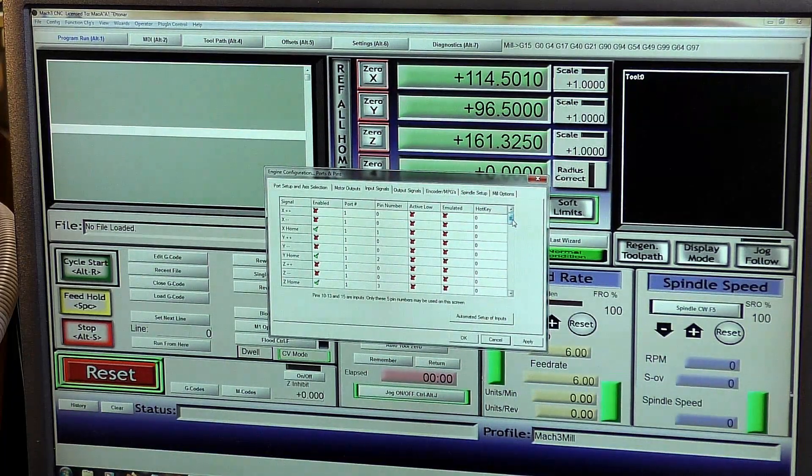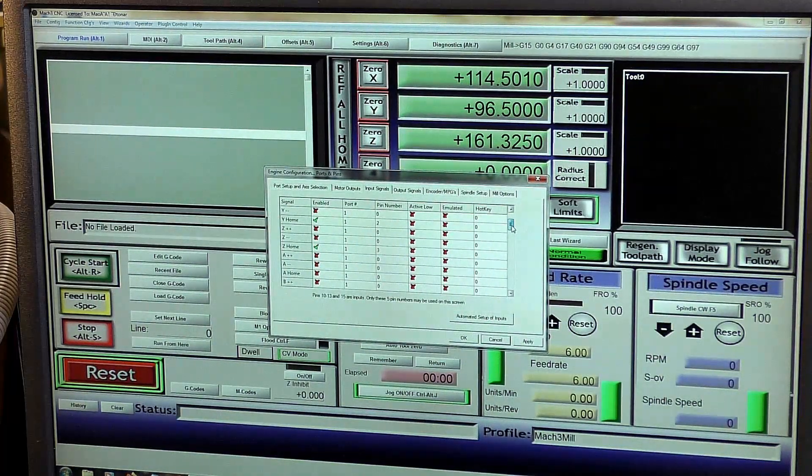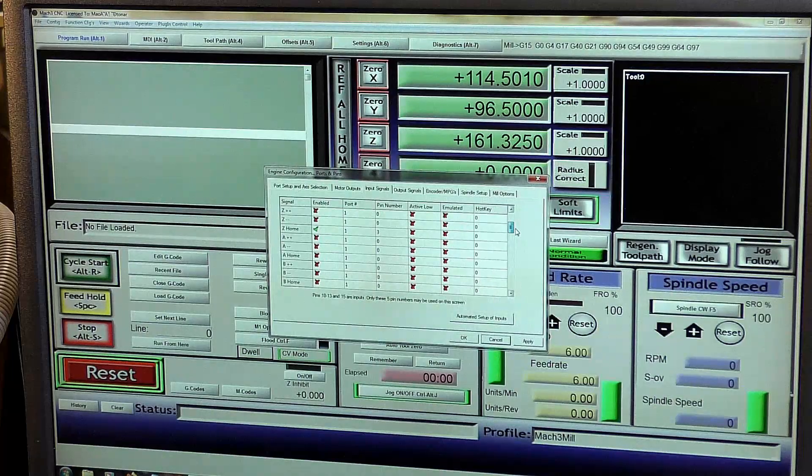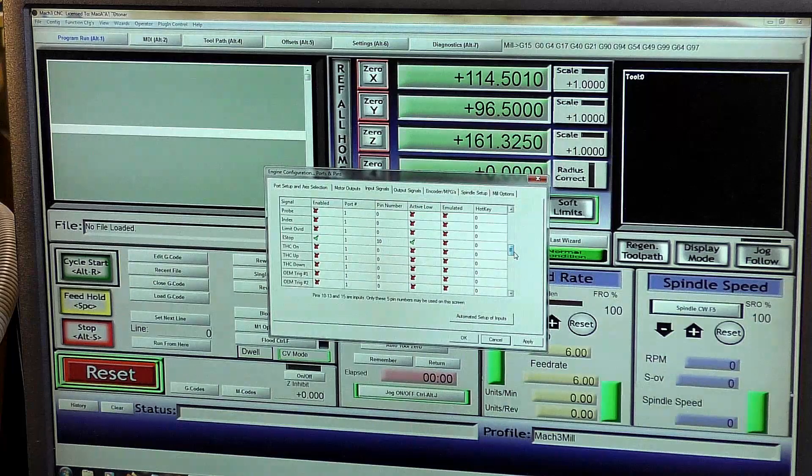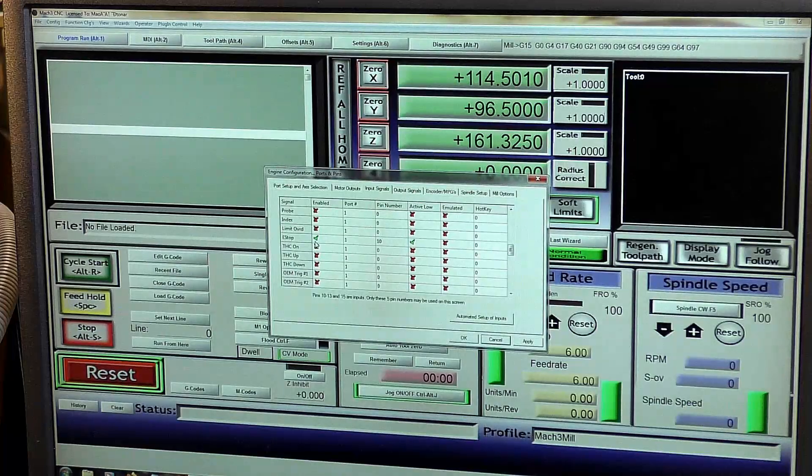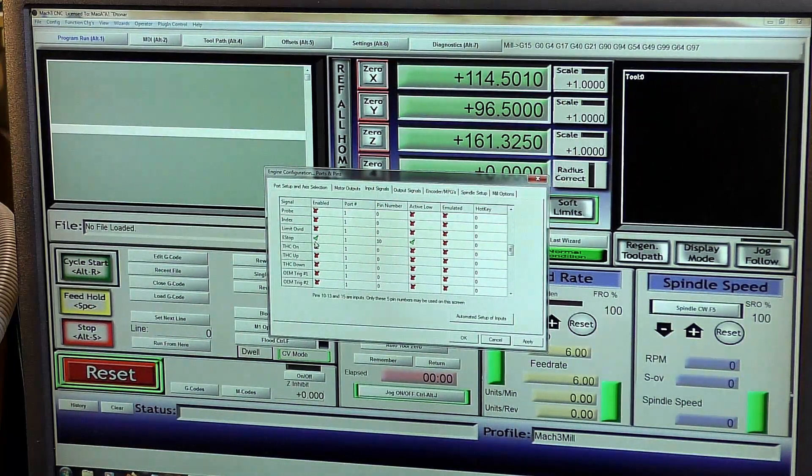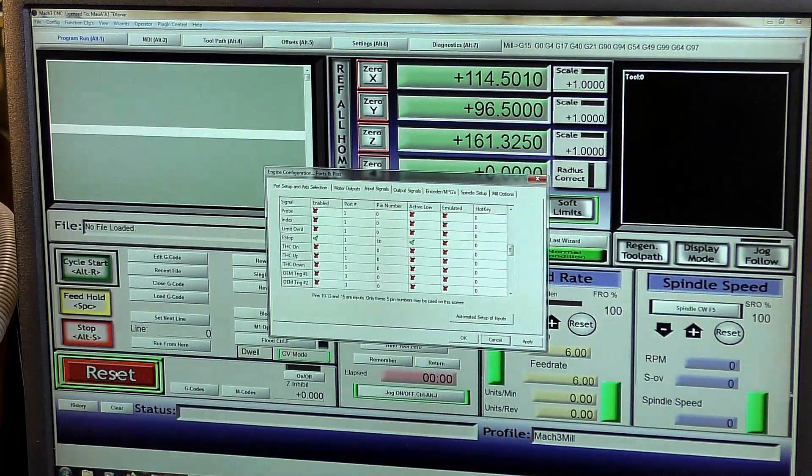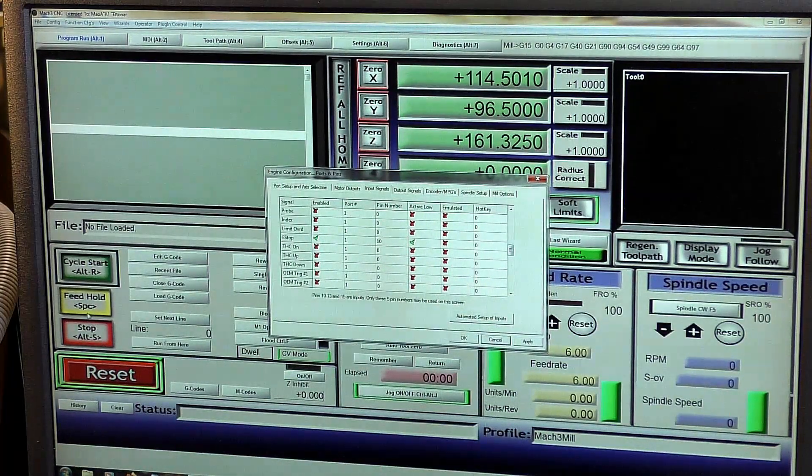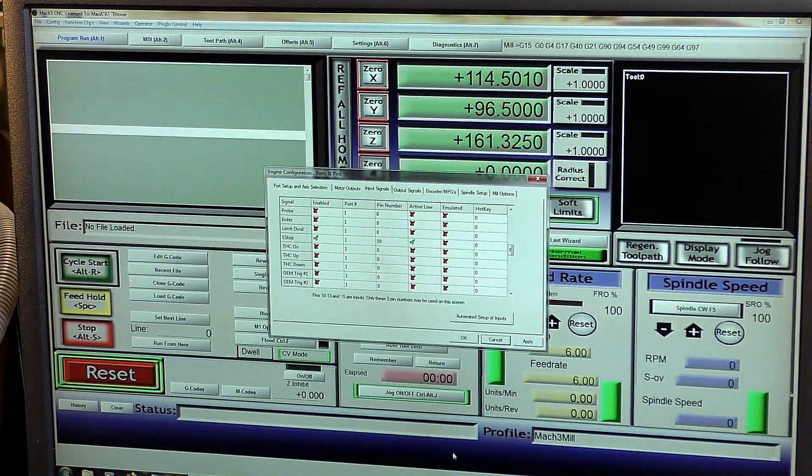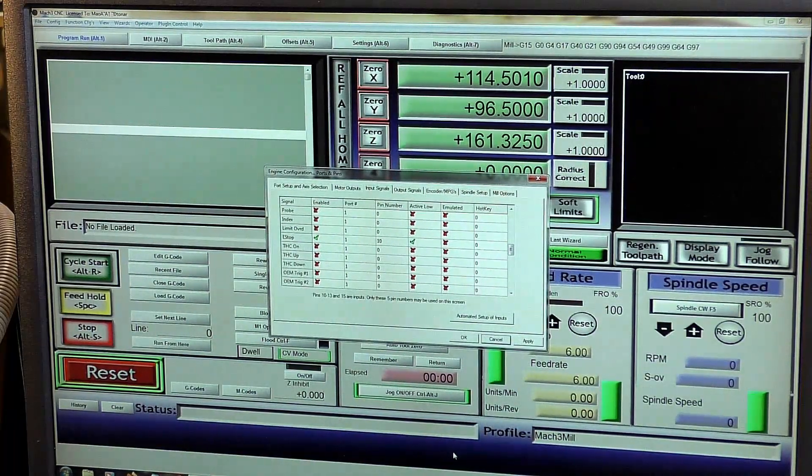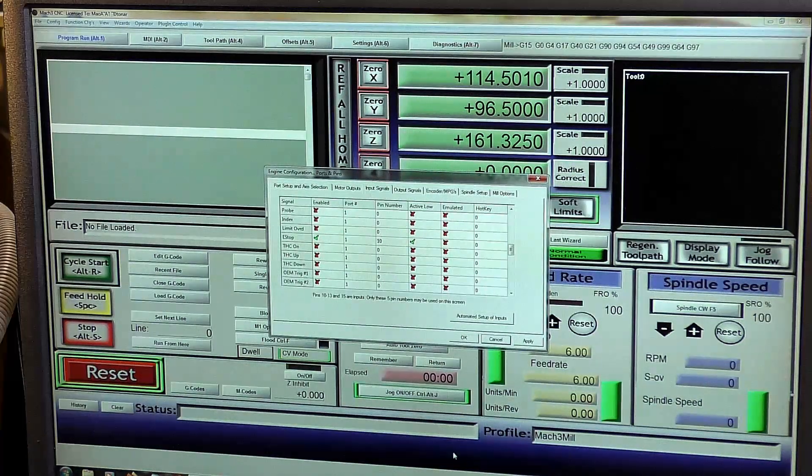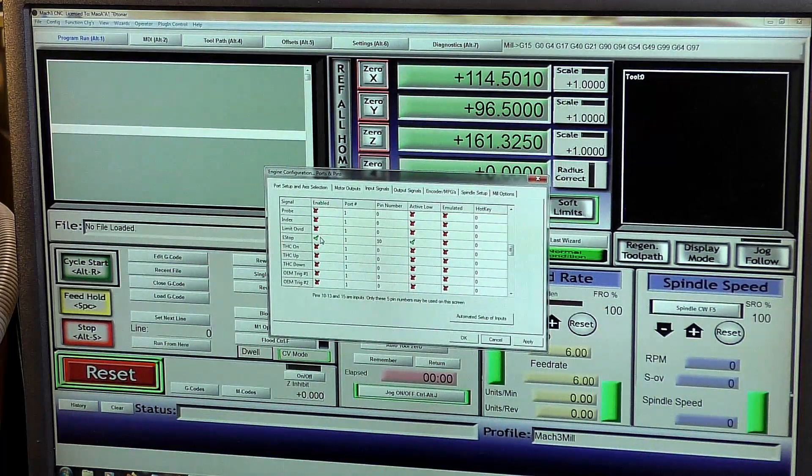And the most important one, and you shouldn't have a CNC router running without, let me see, where is it, down here a bit further, there it is, an e-stop switch. A lot of people run their routers without an e-stop switch. You can't always grab the mouse and come and hit either reset, stop, or feed hold on Mach 3. It's easier, and probably safer, if you see something going drastically wrong, hit the e-stop on the machine. So that's enabled.